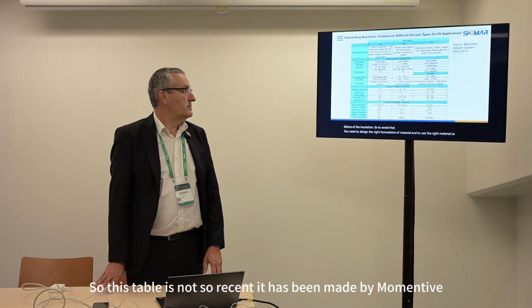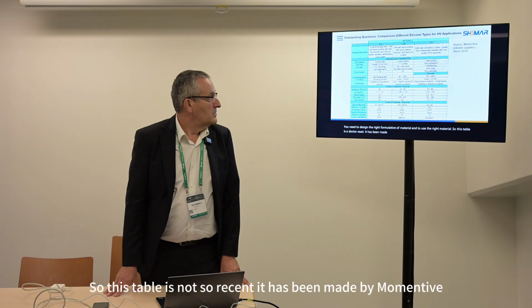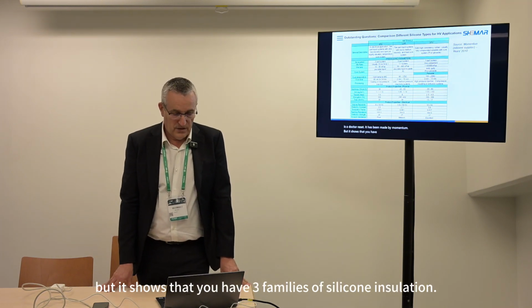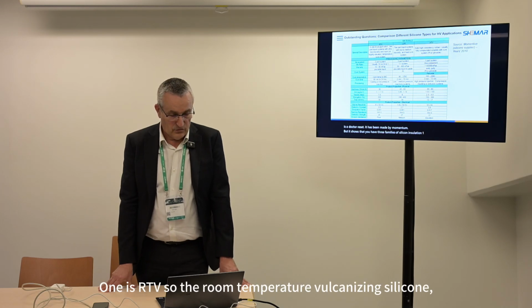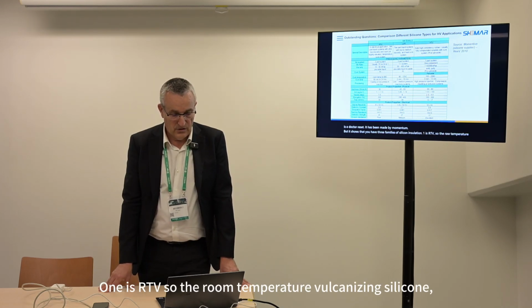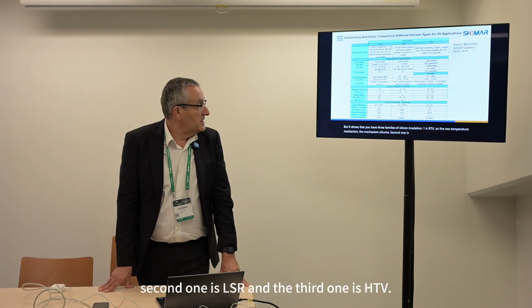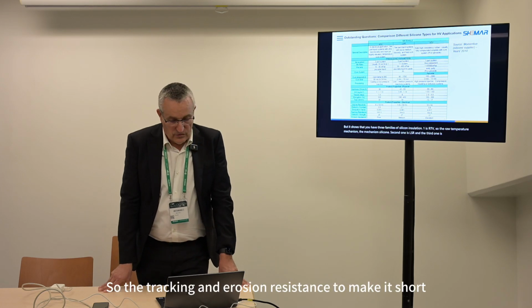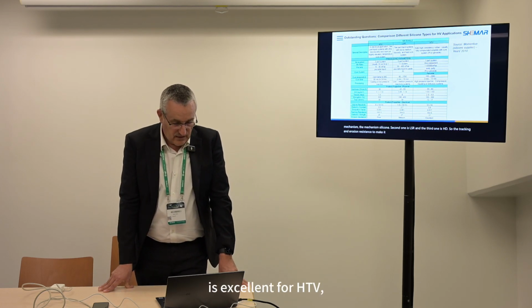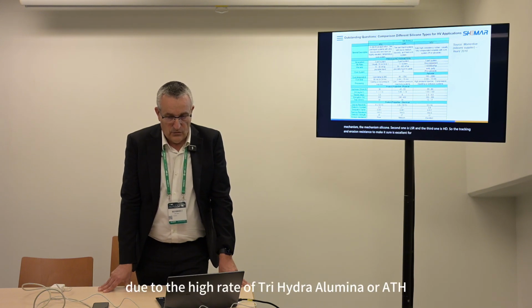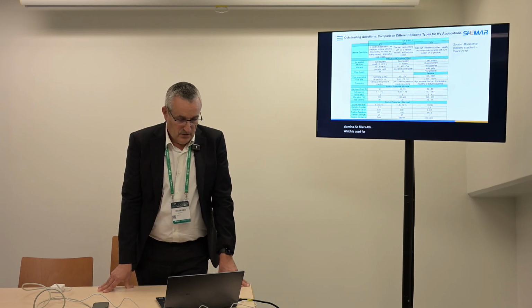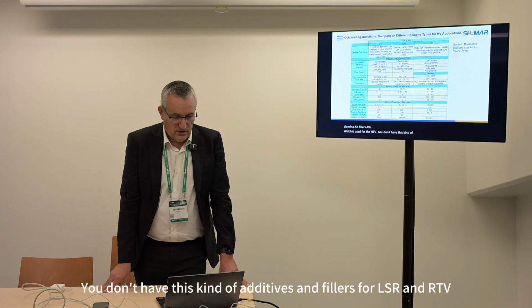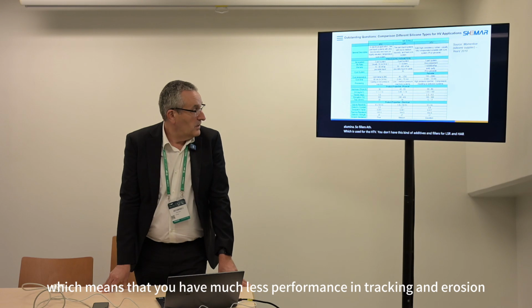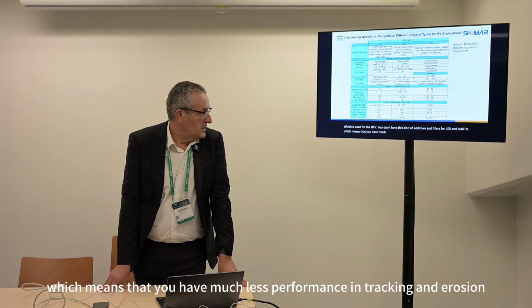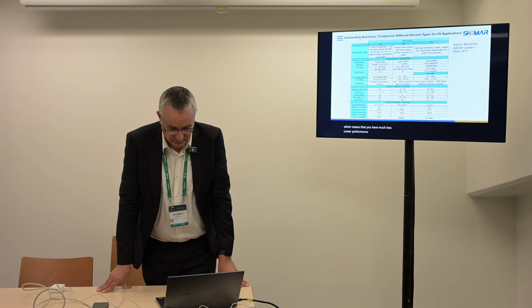So this table is not so recent. It has been made by Momentive, but it shows that you have three families of silicone insulation. One is RTV, the room temperature vulcanizing silicone. The second one is LSR, and the third one is HTV. The tracking and erosion resistance, to make it short, is excellent for HTV due to the high rate of alumina trihydrate fillers, ATH, which is used for the HTV. You don't have this kind of additives and fillers for LSR and RTV, which means you have much lower performance in tracking and erosion.